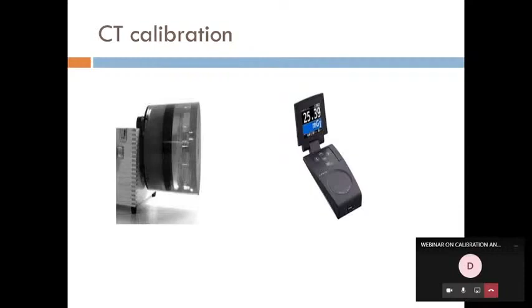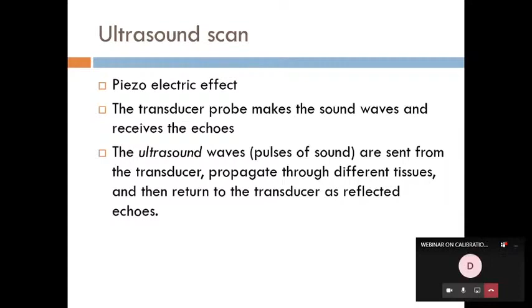Then, ultrasound scan works on the principle of the piezoelectric effect. That is a transducer probe. A transducer converts one form of energy into another form. Ultrasound waves are transmitted from the transducer, and the transmitted ultrasonic wave enters the human body and propagates through the tissues. The same ultrasound wave is returned back, and the returned ultrasound waves are observed by the transducer and converted into a digital format. This is the principle of the ultrasonic machine. The ultrasonic wave will hit the tissues and come back, and that returned ultrasound energy is absorbed in the form of echoes and transferred to the machine.